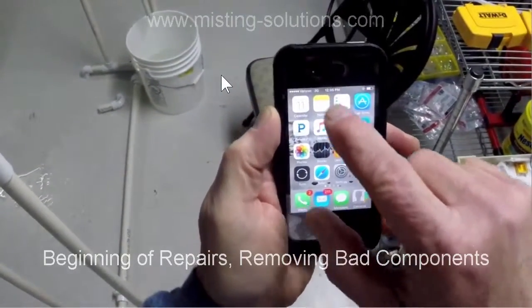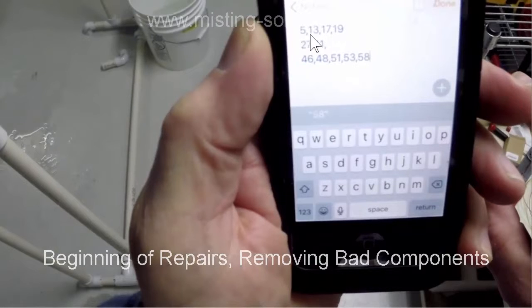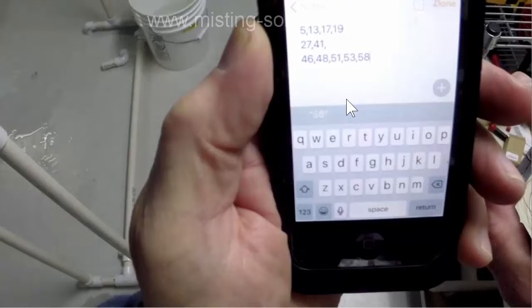Now I'm going to look at that text editor. It's actually a notepad, and you can see the numbering system I use to count which ones are out. The first row has 21 transducers, and numbers 5, 13, 17, and 19 were out. The second row has 20 transducers, and numbers 27 and 41 were out, with 41 being the last one in that row. The third row starts at 42, and 46, 48, all the way up to 58 were out. So that's the numbering system I use, 1 through 62, counting each row and doing a carriage return to show which ones are out on each row.